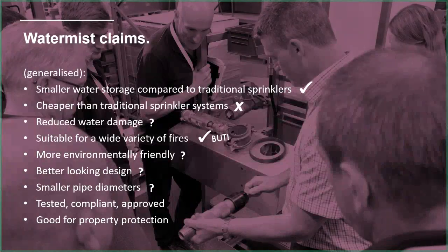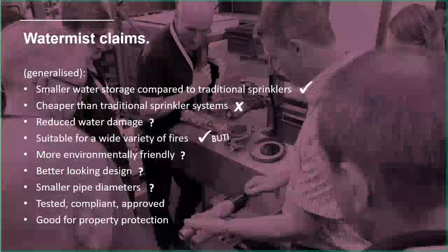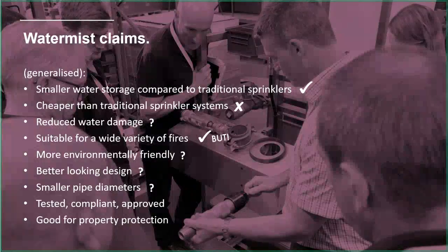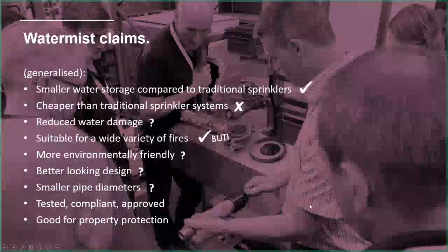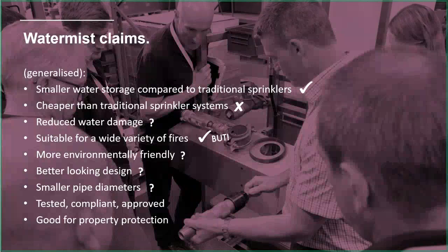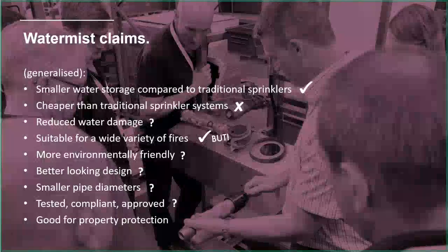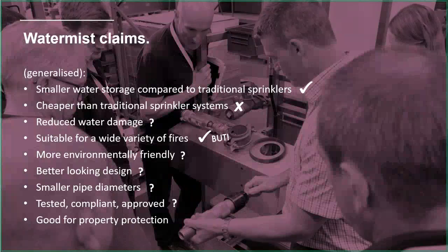Tested, compliant and approved, and this is a big question. Watermist manufacturers will make various claims about what they've been tested to, that they're compliant, that they're approved. I would really encourage you, if you're looking to specify a mist system or thinking of using one, to dig into what exactly it's been tested to. What was the test standard? What were the results? Sometimes you'll find it's been tested to that, but actually failed, or passed that and that but didn't complete that. So yes, it's been tested, but what are the actual results?